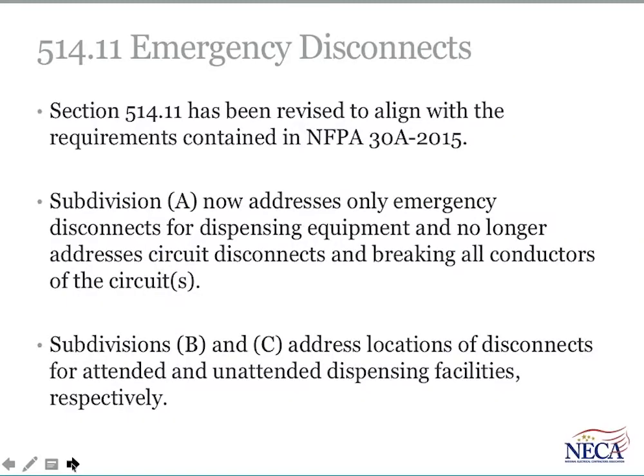Continuing in 514, motor fuel dispensing, Section 514.11 is not new, but it's been revised. It's titled Emergency Disconnects. The changes in this section align with NFPA 30A, which is the parent document for a lot of what you see in Article 514. What happened here is it's divided into two subdivisions. Subdivision A addresses emergency disconnects for dispensing equipment and no longer addresses the circuit disconnecting means and breaking all conductors of the circuit for maintenance type of operations.